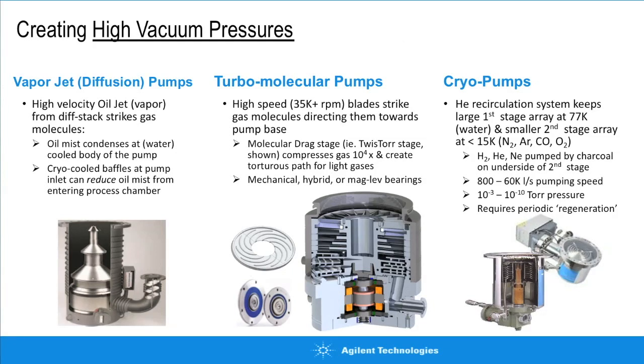Cryopumps use very cold surfaces to capture molecules — there's no exhaust connected. Molecules in molecular flow find their way into the pump body and land on cold surfaces, losing so much energy they can't leave. 77 Kelvin (about -200°C) is very effective at pumping water. A second stage assembly below 15 Kelvin pumps argon, nitrogen, carbon monoxide, and other gases. The downside is that cryopumps only trap molecules and must be periodically regenerated, with regeneration frequency dependent on the gas load.